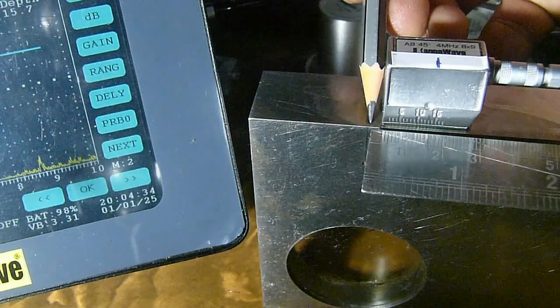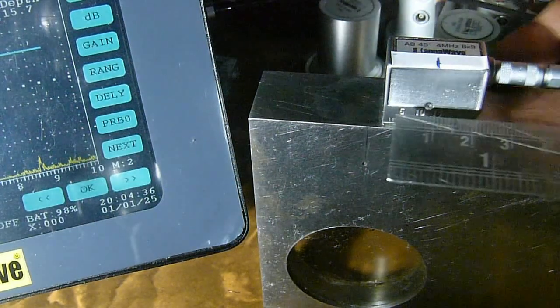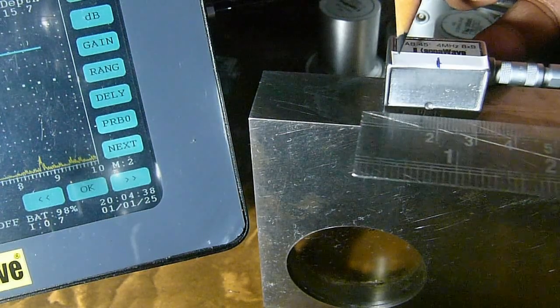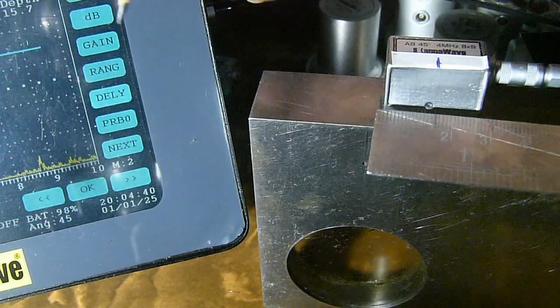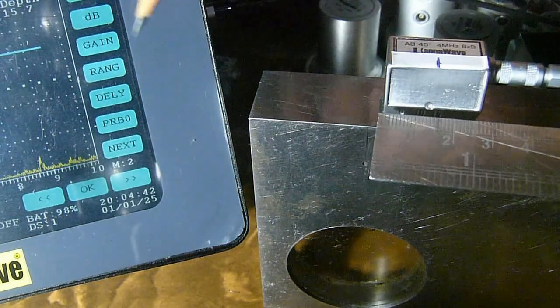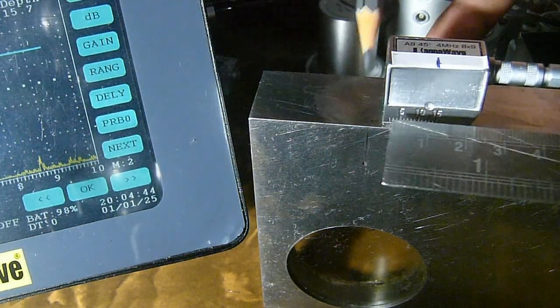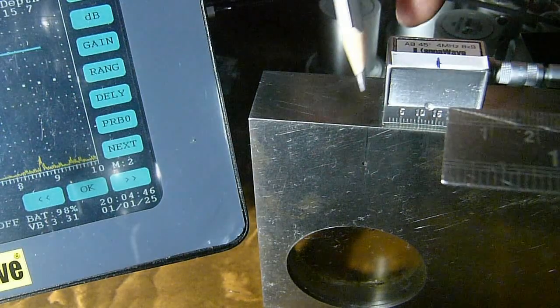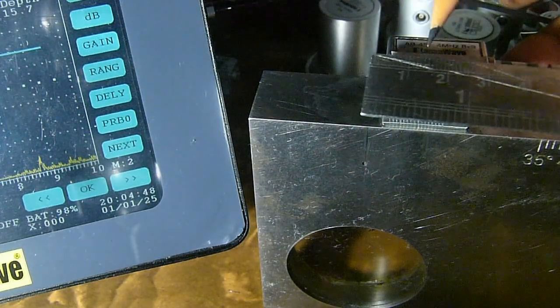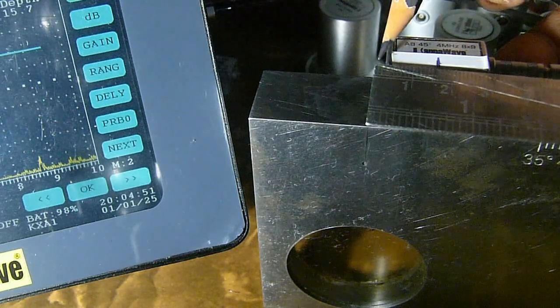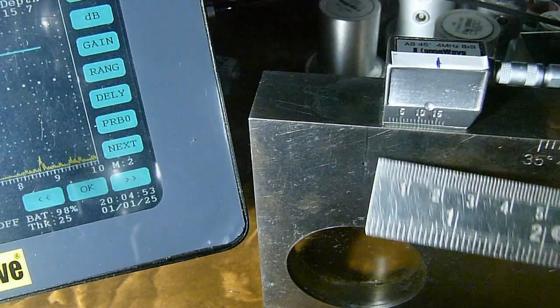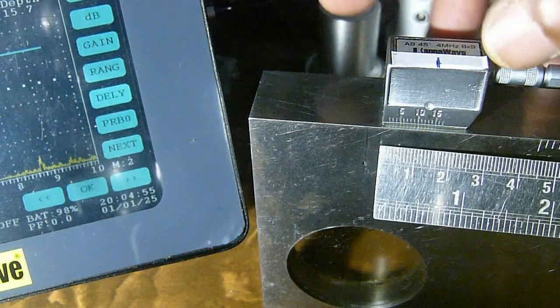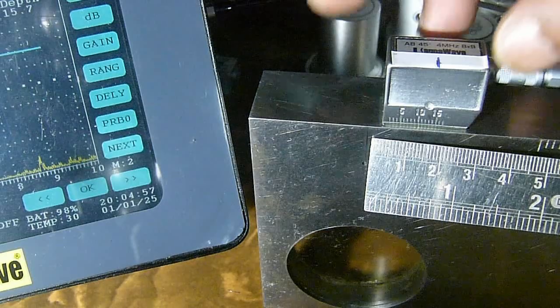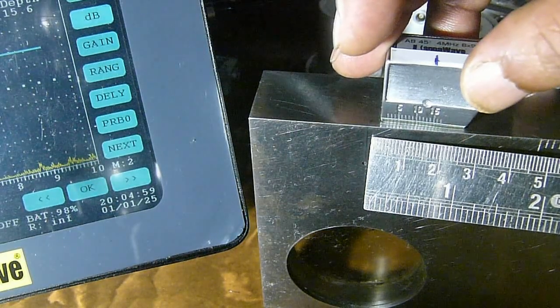For any reason, if the sides are not visible to you or the marking is not available on the top of the probe, then the next option would be to measure from the front of the probe. That is nothing but the reduced surface distance. Let us try on this 50 mm diameter hole. The same probe is used.